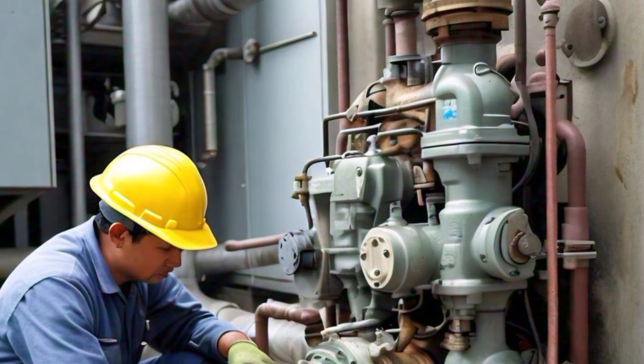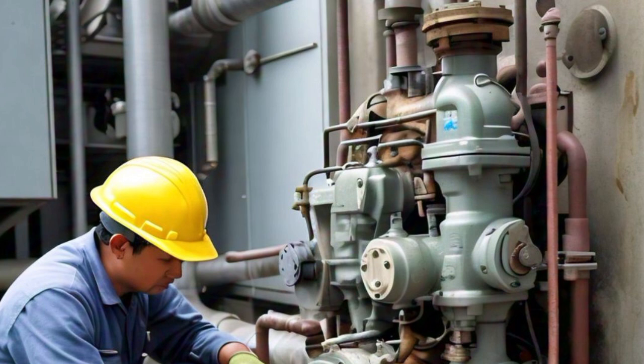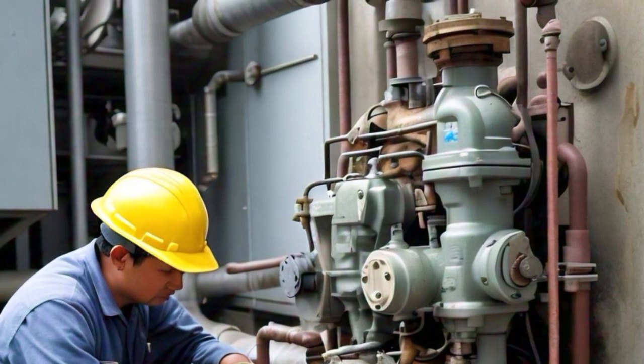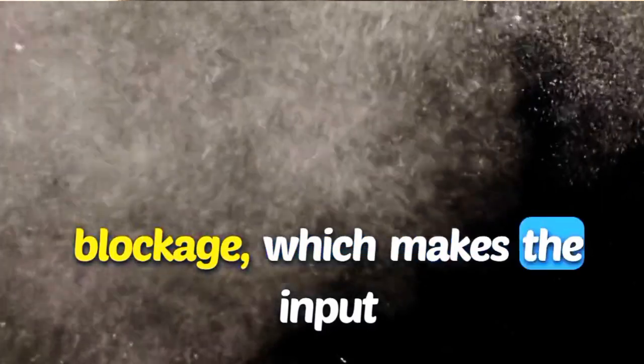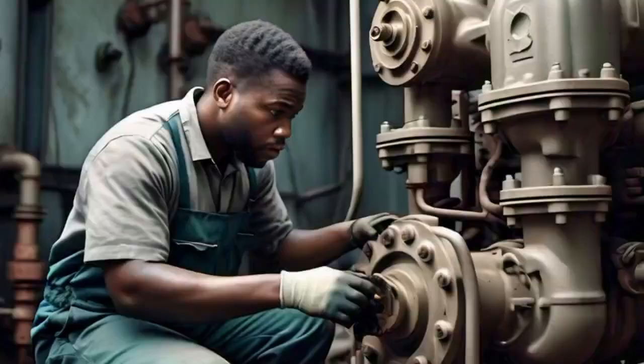Number 4. Blockage of the intake line. The flow rate will be lowered by anything that prevents water from entering the line. A common issue with murky water is debris blockage, which makes the input hose difficult to see. Operators should, however, make sure that the intake is clear of any debris.